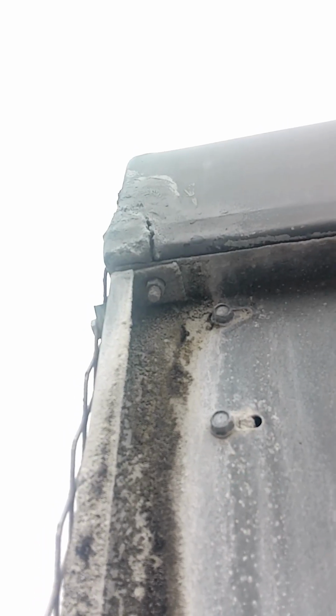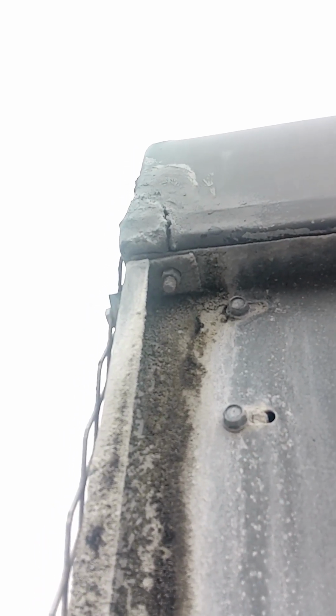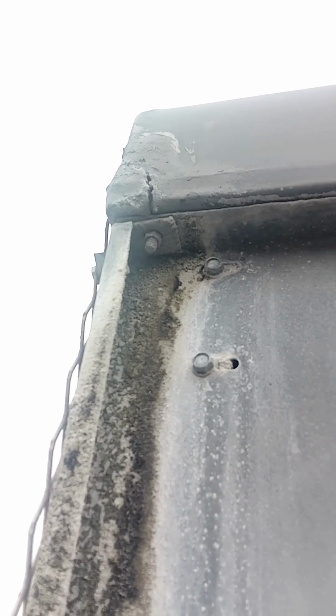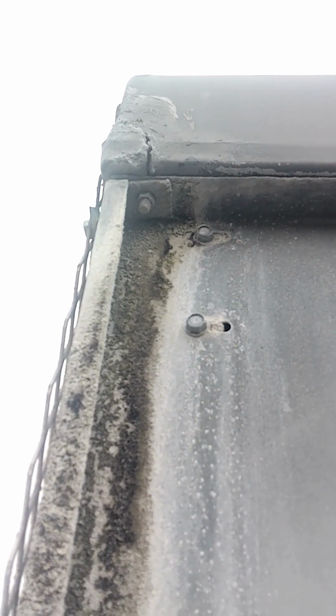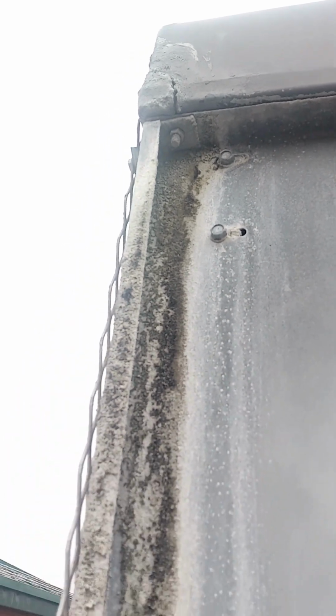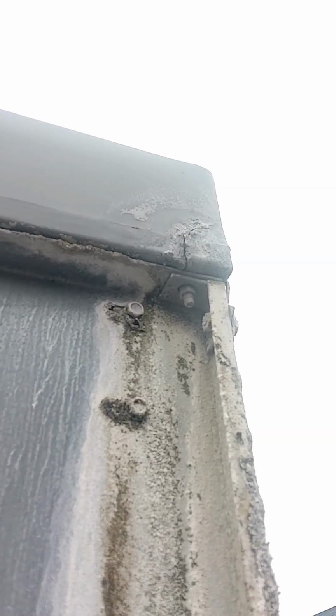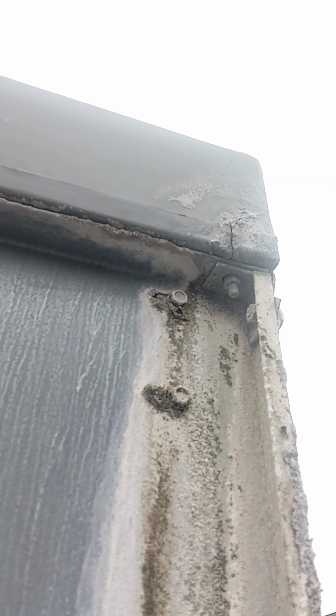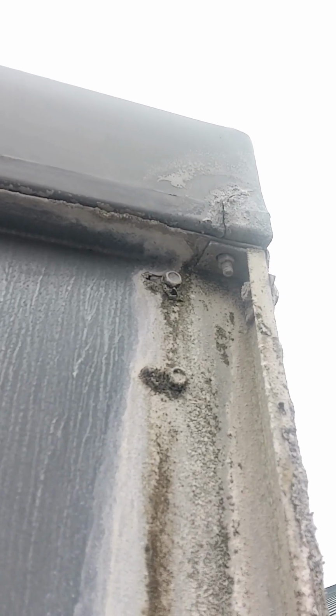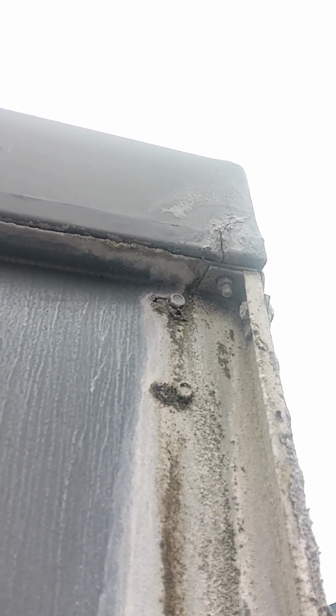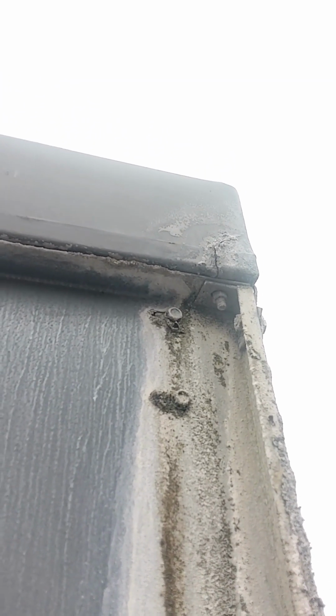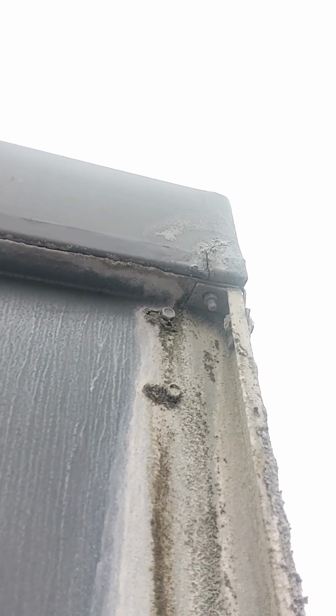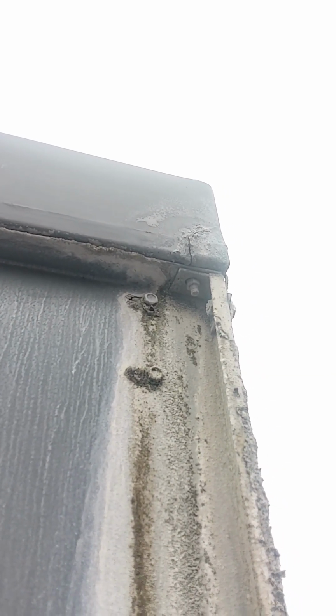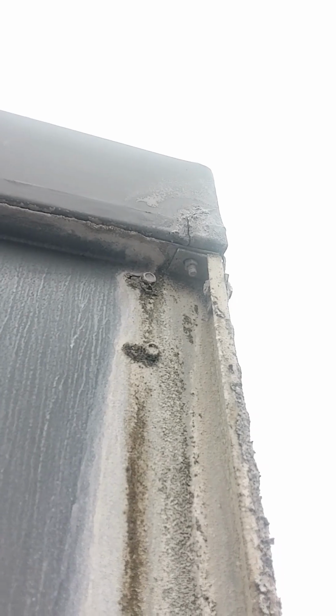Here you can see a crack in the top tank, which allows water to spill out the side of the tower instead of all running down through the material where it's supposed to. Here's a different corner, also cracked. You're going to be able to tell it's been sealed up, plastic welded, and we finally resorted to getting inside there and spraying Flex Seal on the inside in order to minimize leakage and hopefully get through cooling season.